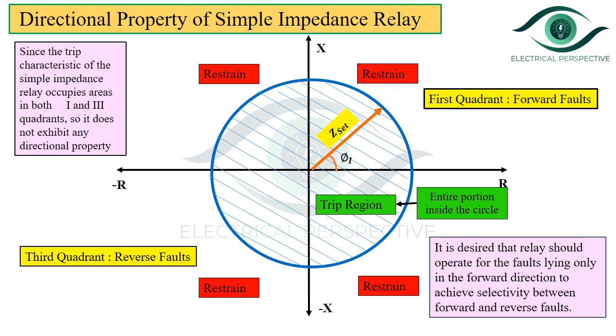Let us discuss the directional property of the simple impedance relay. The first quadrant of the RX plane represents a forward fault, whereas the third quadrant represents a reverse fault. From the RX characteristics, the impedance relay is a non-directional relay because its characteristic is a circle occupying both the first and third quadrants. Thus the relay will trip for a fault in either the forward or the reverse direction. It is always desired that the relay should operate only for faults in the forward direction and never for faults in the reverse direction. Therefore, the simple impedance relay is not useful in situations where selectivity between forward and reverse faults must be maintained.